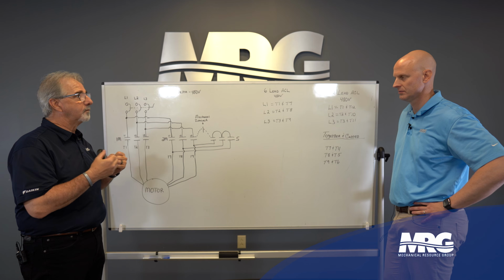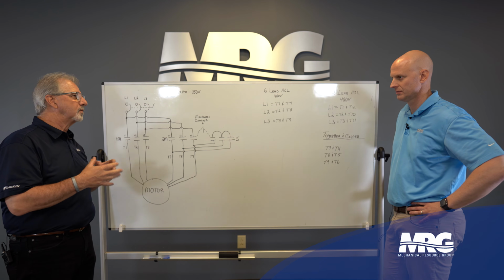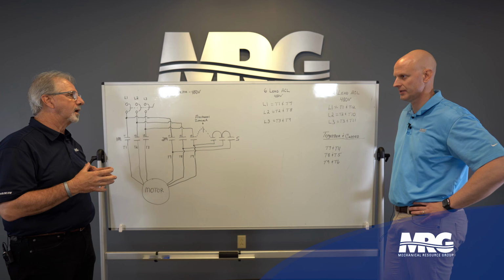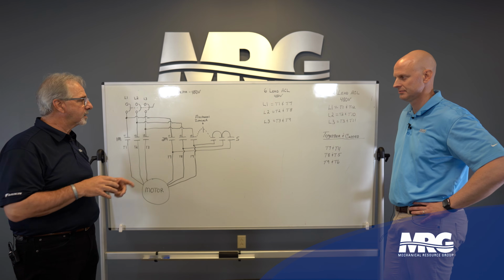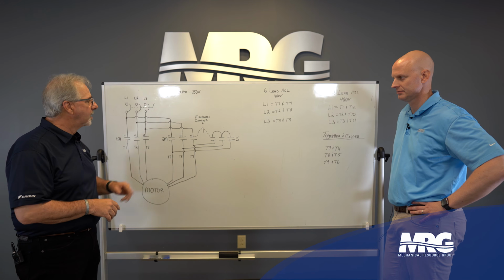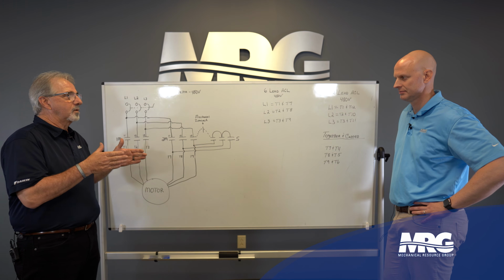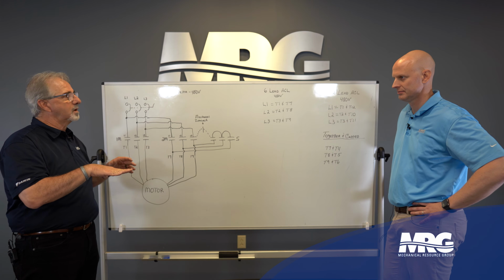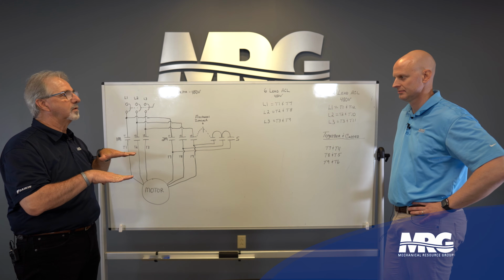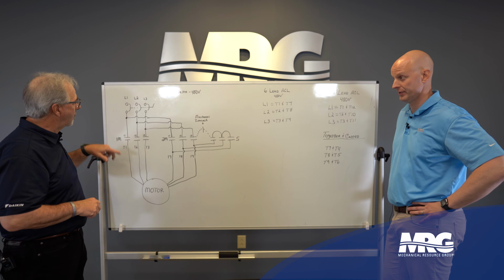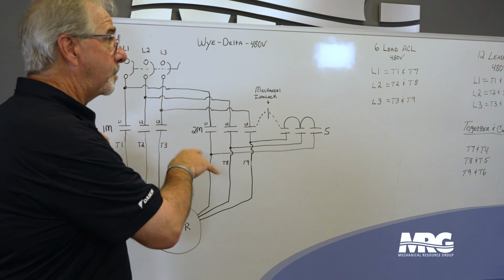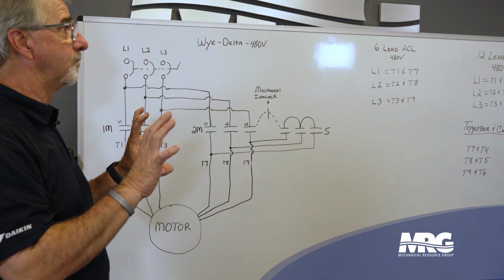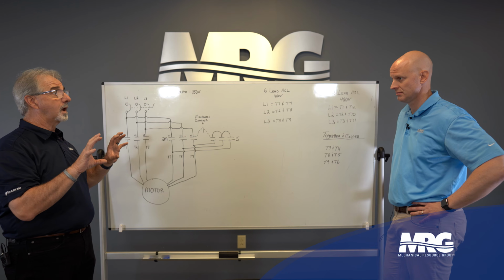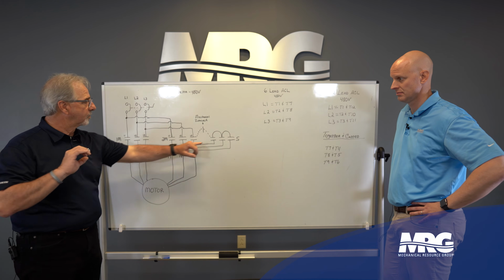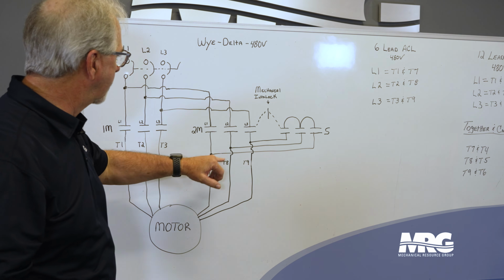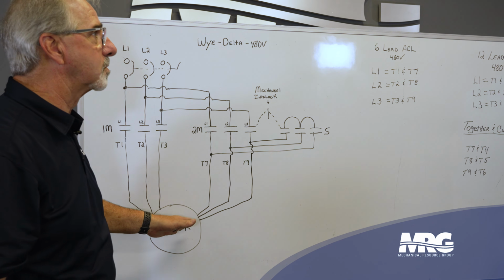So before, when we were at 4 times nameplate, now I can get down to the 2 and 3 times nameplate on startup, okay? But we still have a timer in the circuit, but what we add is a mechanical interlock, okay? So these 2 contactors have a mechanical device in between them that if one is in, the other one can't come in, even if you have voltage applied to the coil, okay? So with the timer, what happens is 1M and the shorting contactor come in first when you send a start command. It times out. When it times out, it drops the shorting contactor out of the circuit and then energizes 2M and connects the rest of the winding.